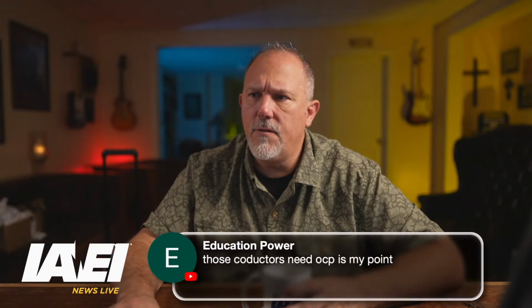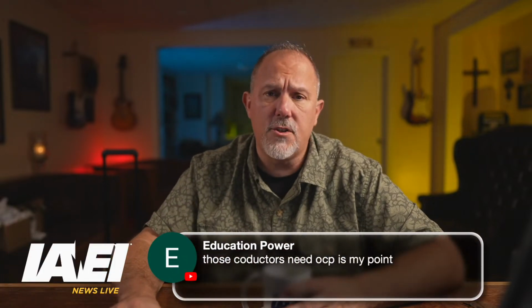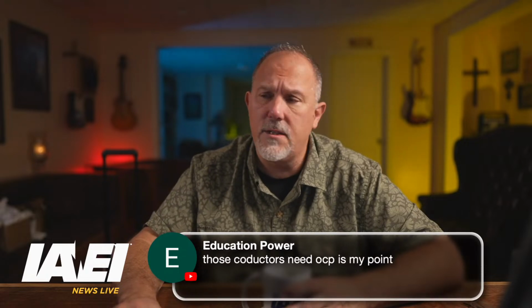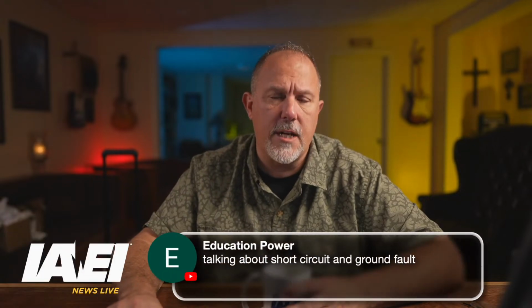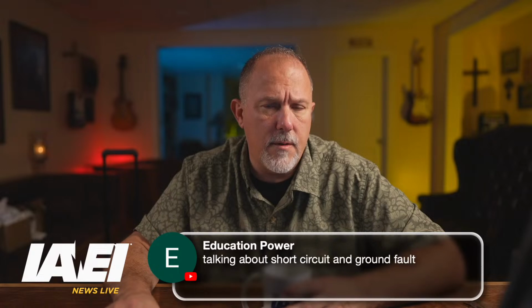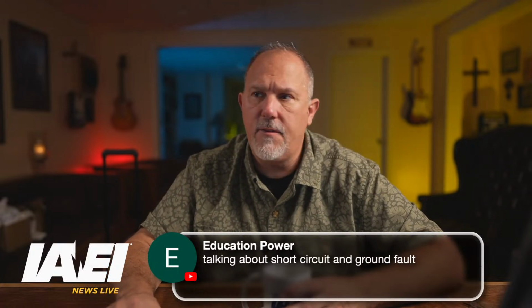Those conductors need an overcurrent device. Yes, absolutely. You have to be downstream of an overcurrent protected device. I would agree with that, Robert. And that is your short circuit and your ground fault protection. Because if your load bank has a problem, you need to have it protected. I would agree with that.